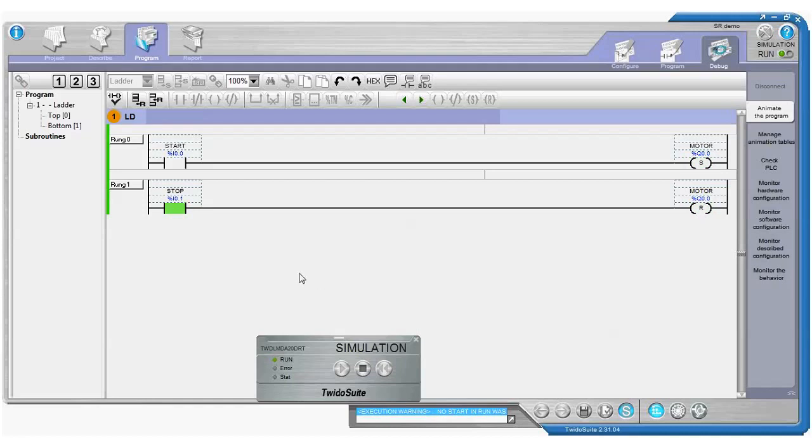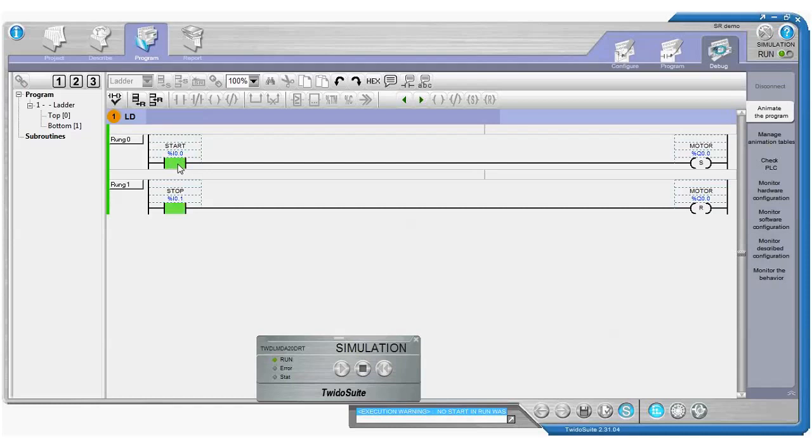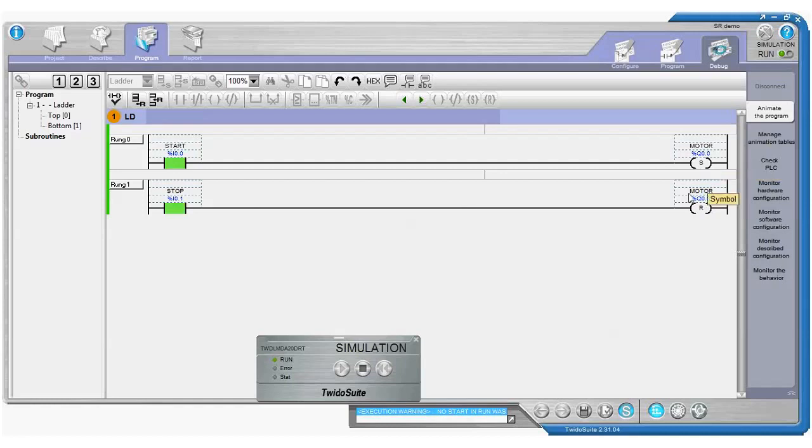If we try and activate both inputs at the same time, yeah, they're both on. And you can see that the second line is taking command. So the first line in the PLC is still for a very short time inside the PLC memory. It uses the on state of the first line to activate the first output. But then as soon as it gets to the second line, the result of the logic in the second line is going to overwrite anything that the first line says. So generally, this way around is a bit safer, making sure that the stop command overrides the start command.